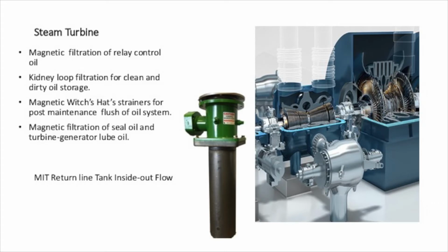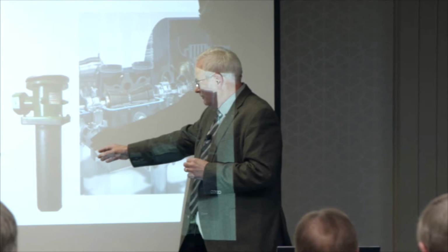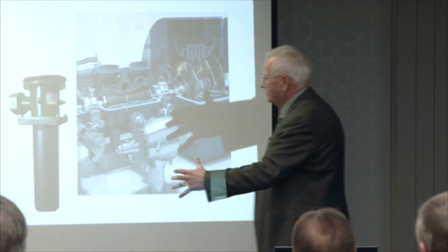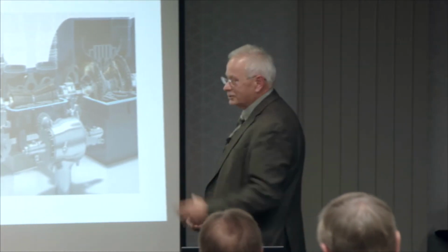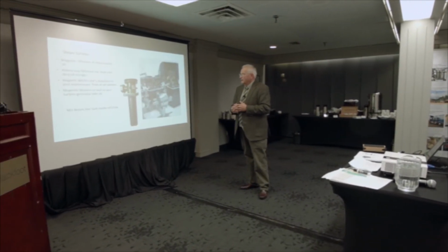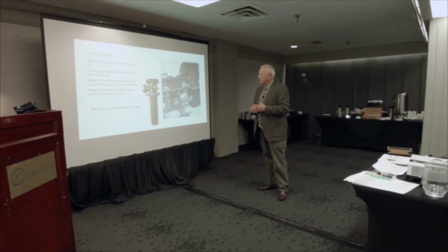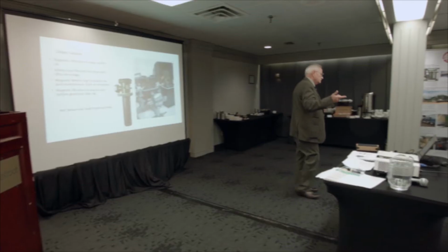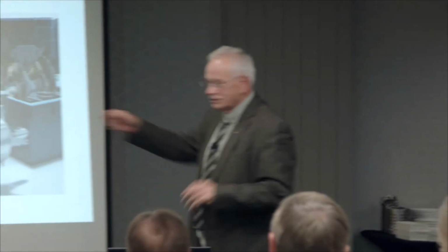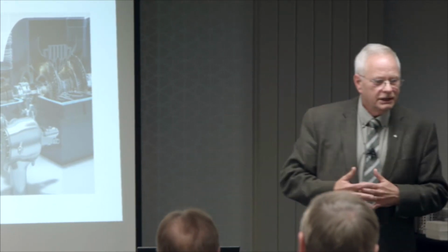So you can put an oil filter, a magnetic filter, in the returns right at the oil tank, right where all your returns come from the turbine. Also, you need a good kidney loop filtration system for your clean and dirty oil system. When you transfer the oil for cleaning it, I would recommend the kidney loop filtration system. Also, if you're recommissioning after maintenance periods, you do an oil flush, you can buy the witches' hats. Now, we used to use those witches' hats just on original commissioning, but you can just slip them in and do a circulation and clean up any particles from there.